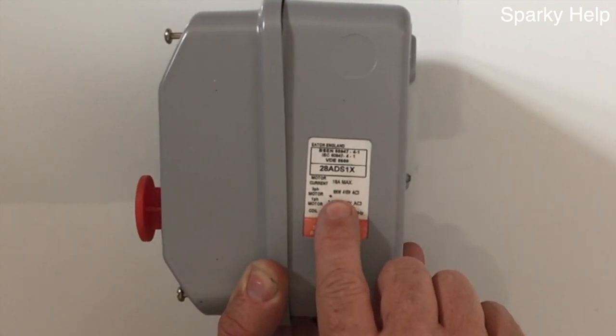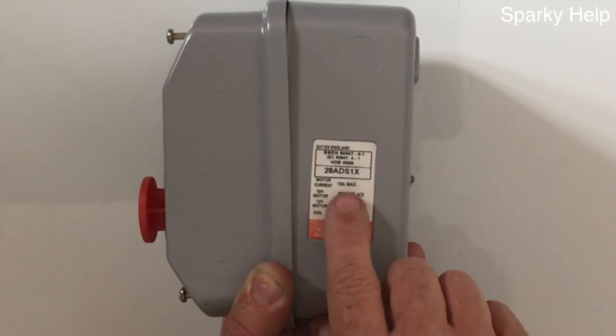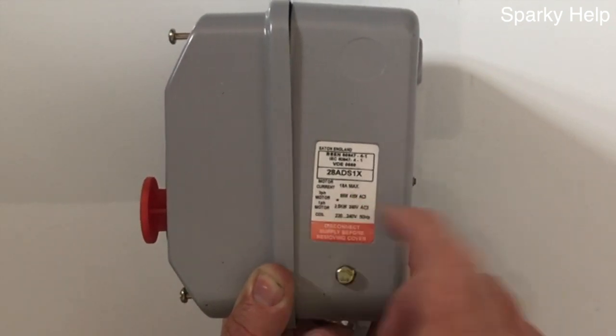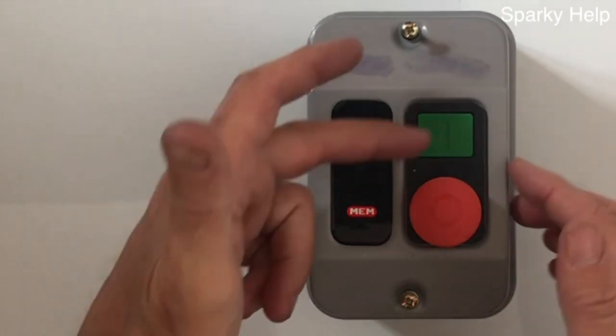So this will do a three phase nine kilowatt or a two and a half kilowatt single phase, maximum motor current of 18 amps. So anything up to that size from this particular motor starter which is just an on-off.